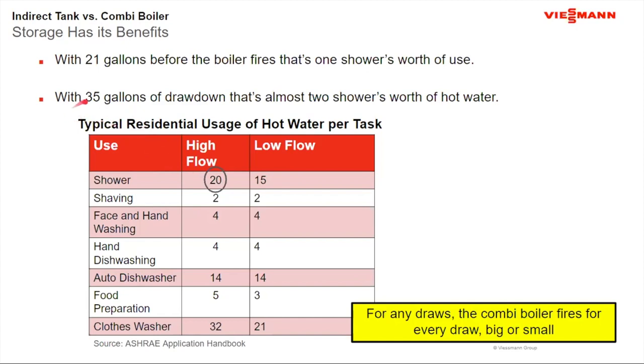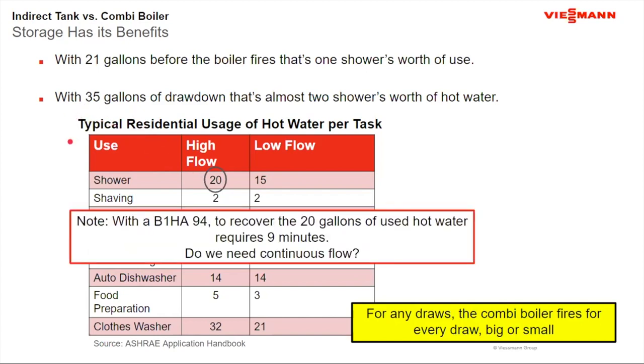Now, a lot of times when we look at these numbers, the question always comes about recovery, okay? If I do a 94,000 BTU input boiler, let's call it 89,000 out, and I just take one shower, I use 20 gallons of water, and let's say after that shower, the boiler goes into recovery mode. It will take about 9 minutes for that boiler to now reheat that 20 gallons of cold water that just came in. And a lot of times people say, I do a combi because I have continuous use. It's a continuous number. Continuous is not how we use water, and showers happen to be probably the high demand item in the house as far as repetition during the course of that peak hour.